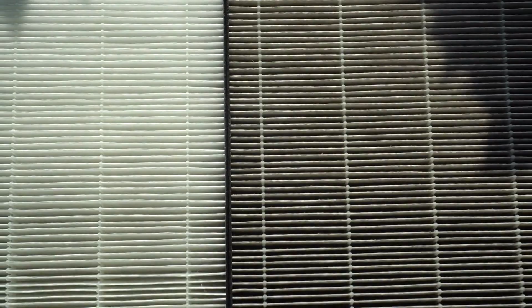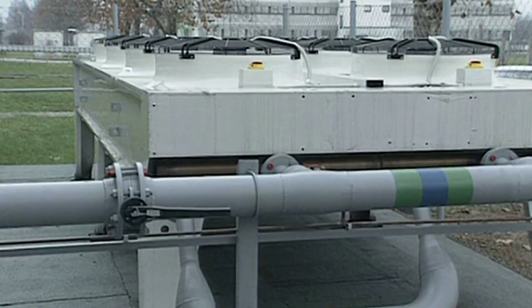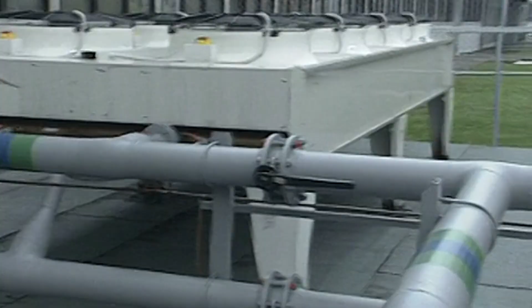Once the air is compressed, purification becomes critical. Water vapor and carbon dioxide must be removed almost completely. If they were allowed to remain in the air, they would freeze during the cooling process, forming ice or solid carbon dioxide. These solids would clog pipes, valves, and heat exchangers, potentially shutting down the entire system. To prevent this, the air is passed through specialized purification units that use adsorption materials designed to trap moisture and carbon dioxide on their surfaces.